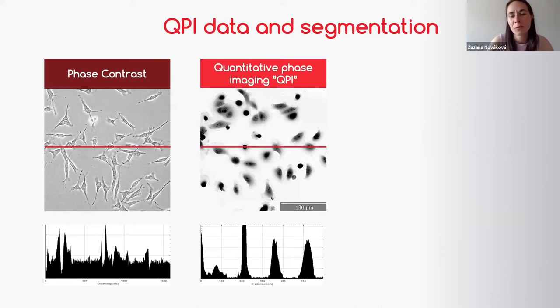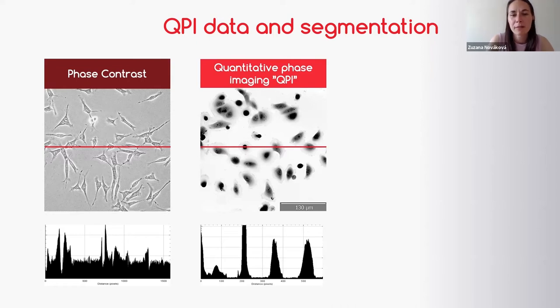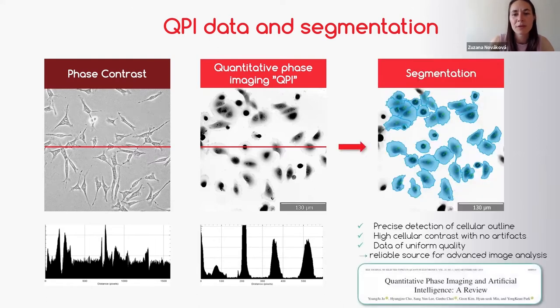There is something more about this image — the background of such image is really flat. As you can see from the lines displaying the profile of such image compared to the phase contrast method, which suffers from white halo artifacts around cells, the background in the QPI image is really flat. Therefore these data are great for image analysis, because you can easily not only discriminate background and objects, but also easily segment the objects.